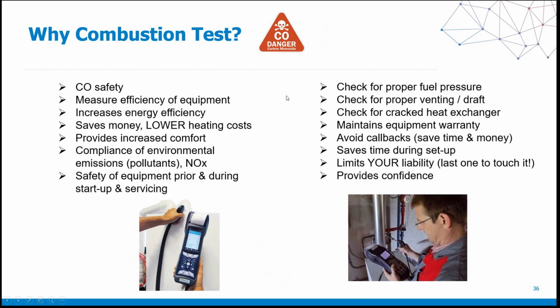Why combustion tests? Well, first and foremost, it's for the safety of the occupants and your own personal safety. We also want to measure the efficiency of the equipment, making sure that it is operating in the most efficient way possible and that we're not having any unsolicited losses, and maintaining the proper operating conditions of the equipment. We also want to save money, having lower fuel bills, lower heating costs and the like. Very important when we talk about efficiency.